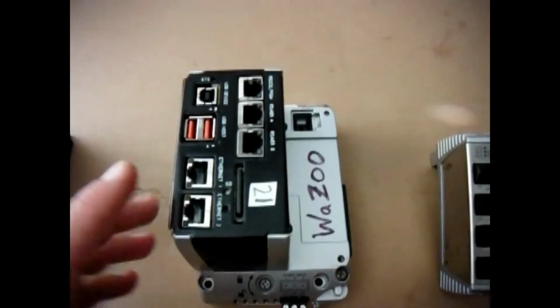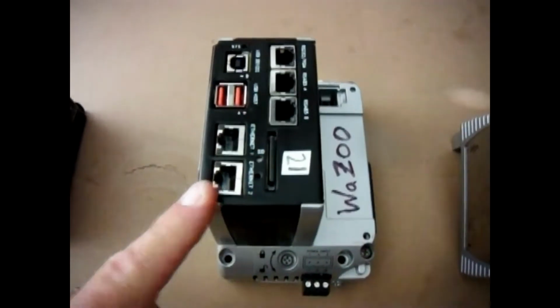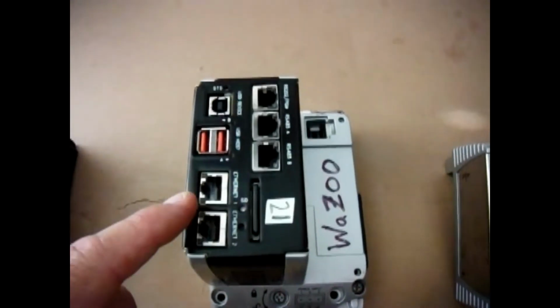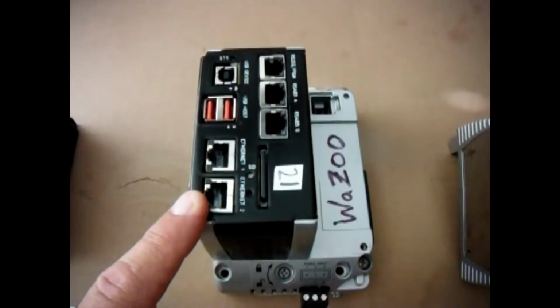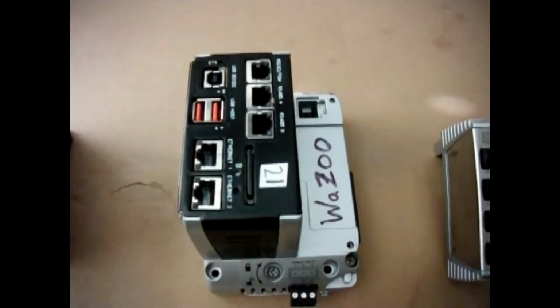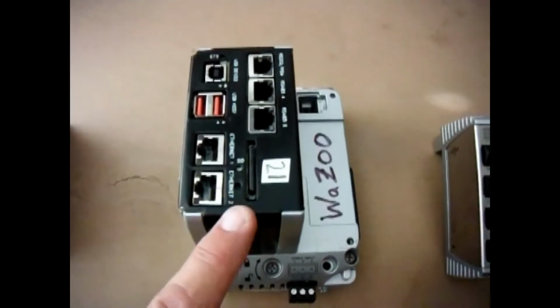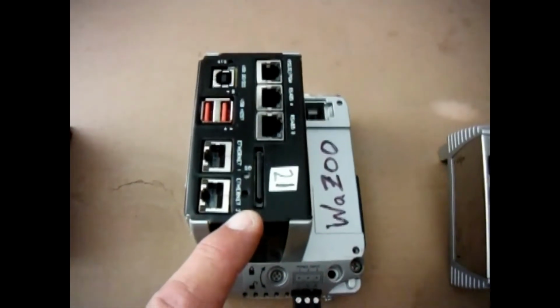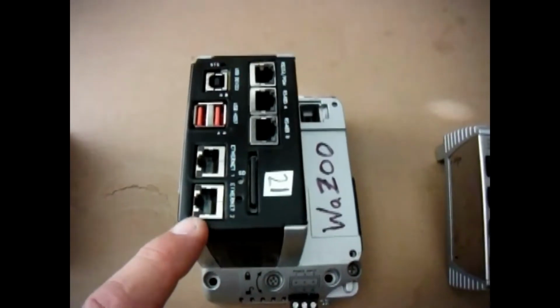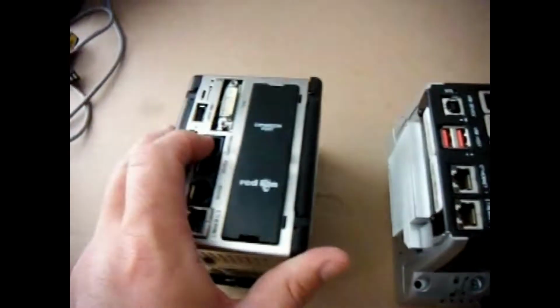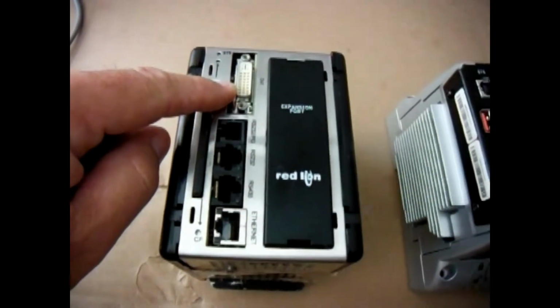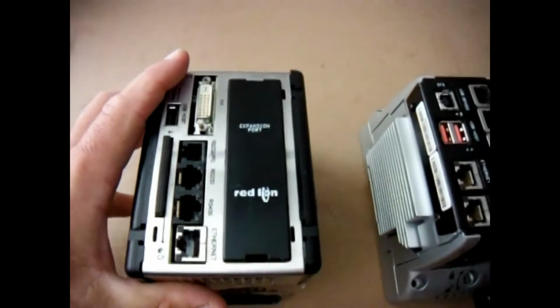One of the big reasons I like to do that is because with the Ethernet port and with today's smart TVs, particularly the LG and the Samsung brand, you can pull up the web server through this and you get use of the whole TV. Plus, this one running on Crimson 3.1 allows up to 20 users or 20 TVs could be looking at the web page for that. Whereas with the old Productivity Station, you have one DVI output here, really goes on to one TV, unless you buy some kind of HDMI splitter, which of course increases your cost. This thing is about half the price, actually a little less than half the price of this guy, brand new, and has a ton of new features.